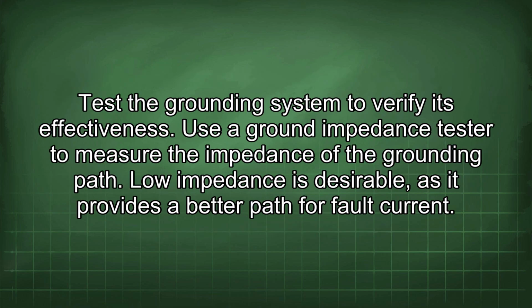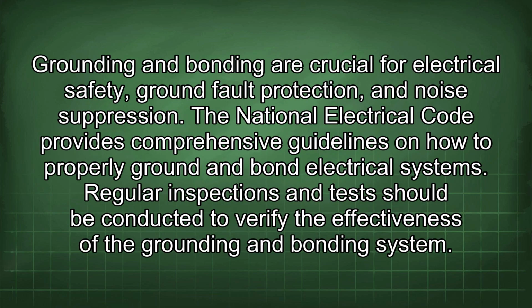Test the grounding system to verify its effectiveness. Use a ground impedance tester to measure the impedance of the grounding path. Low impedance is desirable as it provides a better path for fault current. Grounding and bonding are crucial for electrical safety, ground fault protection, and noise suppression. The National Electrical Code provides comprehensive guidelines on how to properly ground and bond electrical systems. Regular inspections and tests should be conducted to verify the effectiveness of the grounding and bonding system.